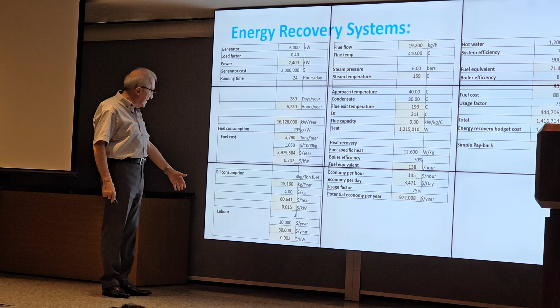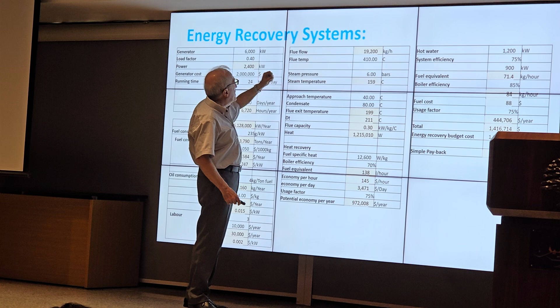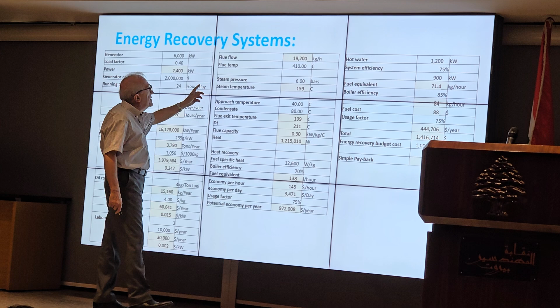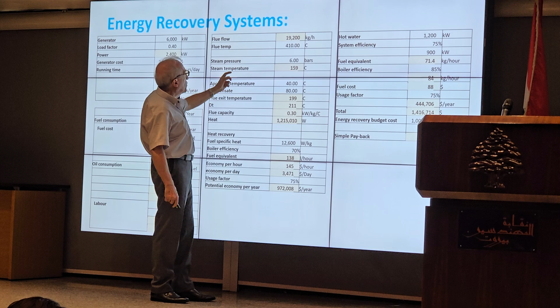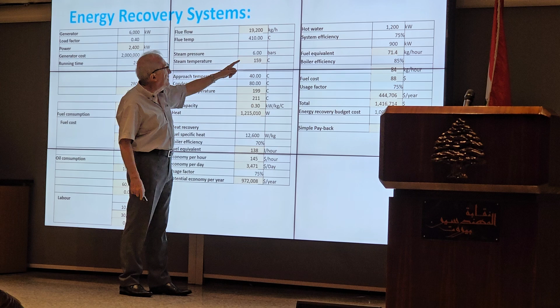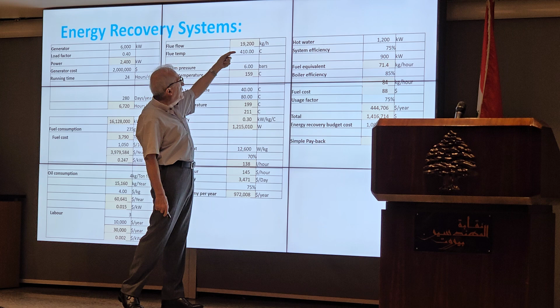So we go through this calculation. We know how much the gas flow is, 19,000 kilogram, 19 ton per hour, and at what temperature, and we know what temperature we need. We need steam at 160 degrees, 6 bar. So we consider that the flue exit is 200. So we will recover the heat from 410 to 200. And we have put here that the system efficiency is 70%.